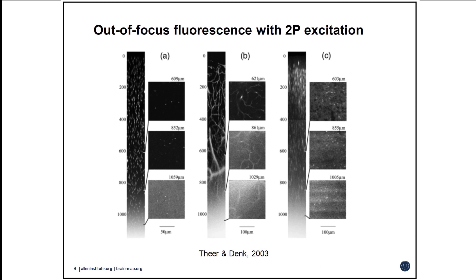Out-of-focus fluorescence is something that's been known and understood since the early 2000s. With two-photon microscopy, as you image very deep into the tissue, you naturally have to increase the illumination intensity to maintain significant excitation in the deeper layers. As you get down towards around about a millimeter, the intensity at the surface becomes high enough that you end up with significant excitation of surface structures when you're trying to image deep. You misassign the photons from the surface to these deep-lying pixels, resulting in this excess fluorescence from out-of-focus locations, which destroys your contrast.